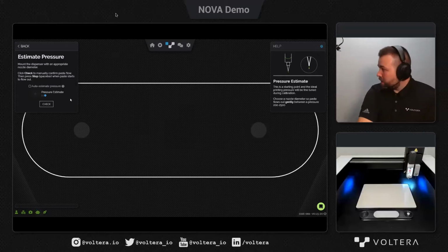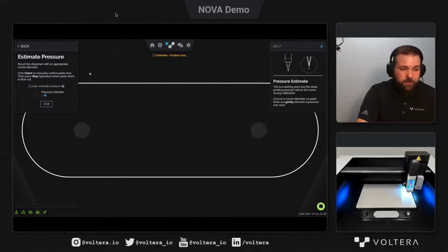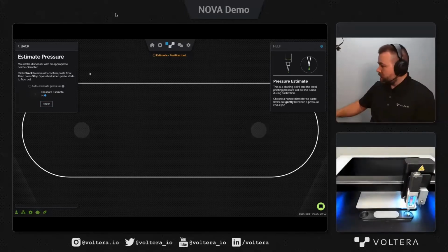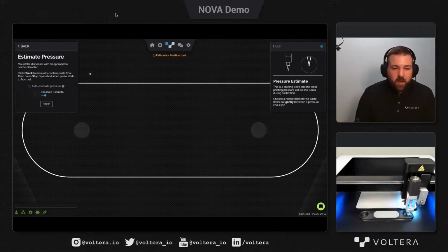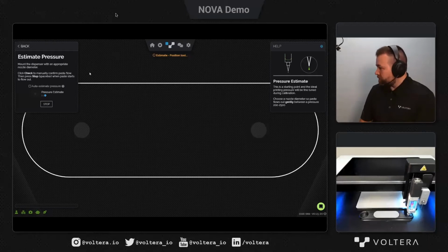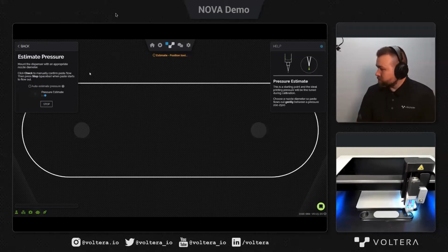All right, so we are fully heated up here. So I'm just going to go ahead and hit check for the pressure estimate. What we're doing here is getting a baseline starting point before we start the calibration procedure. We just want to know a good starting pressure to get a rough start for our calibration process. So we can see Nova, the dispenser, interacting with the XYZ positioner tool, much like the probe did.